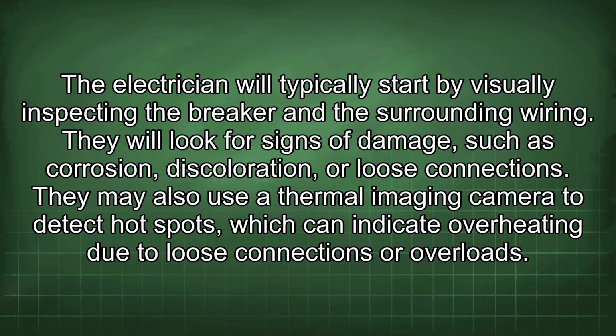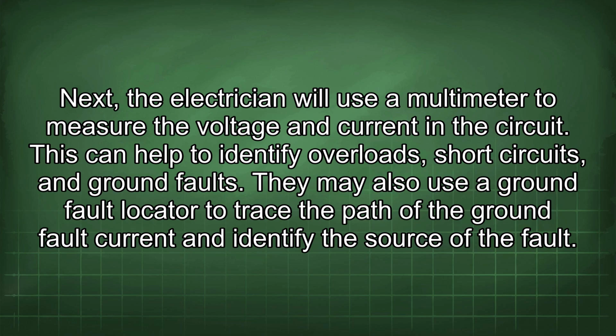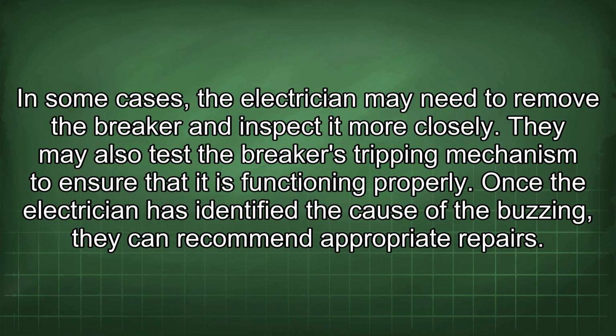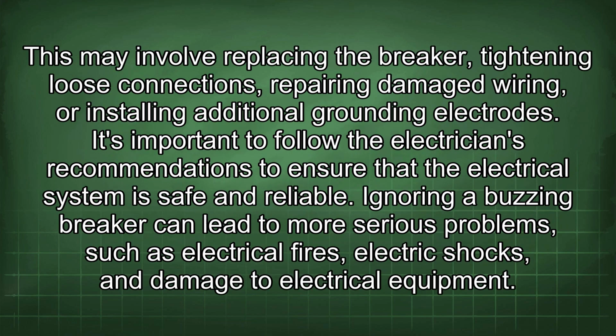or overloads. Next, the electrician will use a multimeter to measure the voltage and current in the circuit. This can help to identify overloads, short circuits, and ground faults. They may also use a ground fault locator to trace the path of the ground fault current and identify the source of the fault. In some cases, the electrician may need to remove the breaker and inspect it more closely. They may also test the breaker's tripping mechanism to ensure that it is functioning properly. Once the electrician has identified the cause of the buzzing, they can recommend appropriate repairs. This may involve replacing the breaker, tightening loose connections, repairing damaged wiring, or installing additional grounding electrodes.